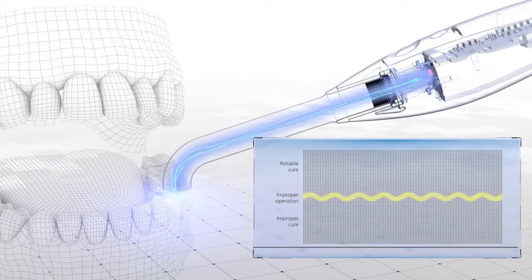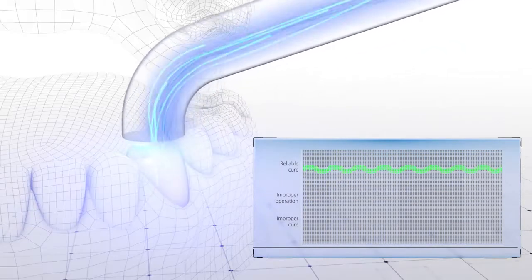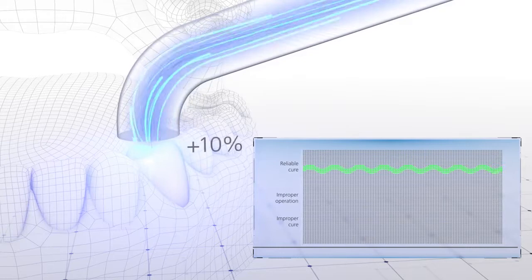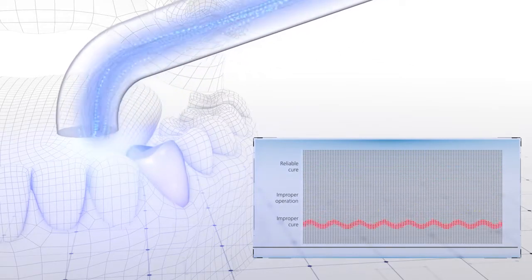The curing unit will vibrate to alert the user about the improper operation and the curing time will automatically be extended by 10% if the movement may prevent the material from curing properly.